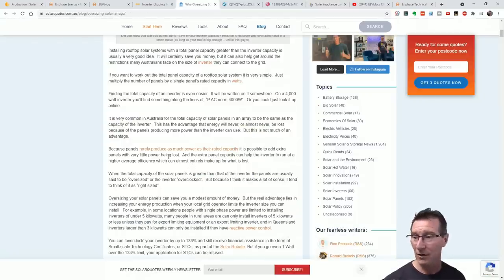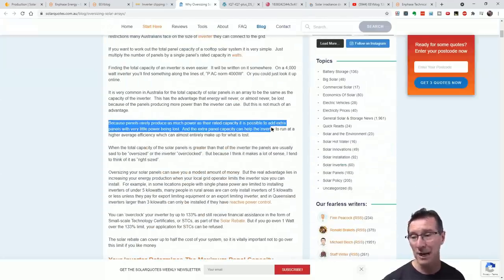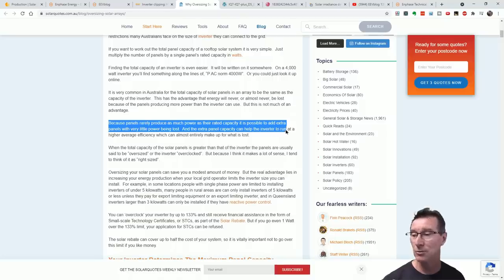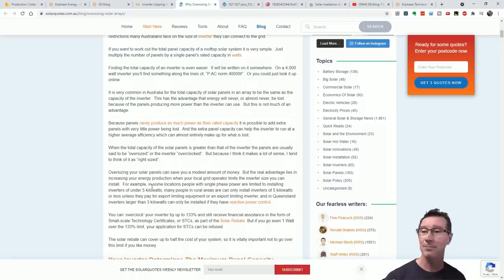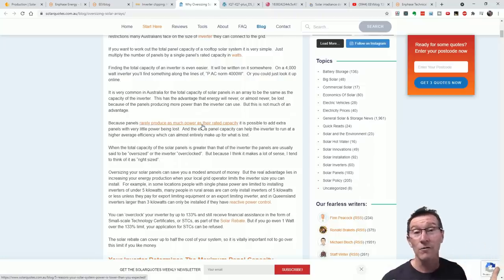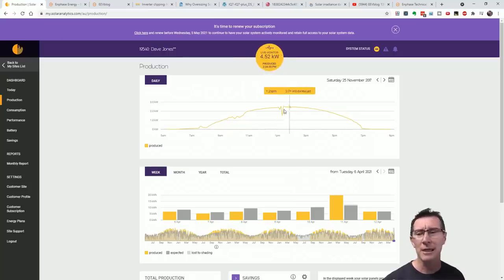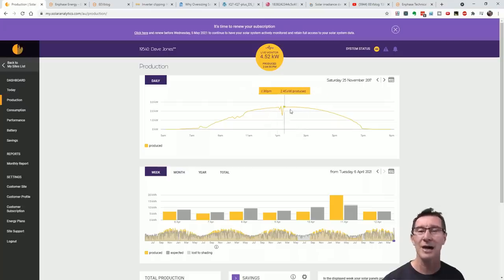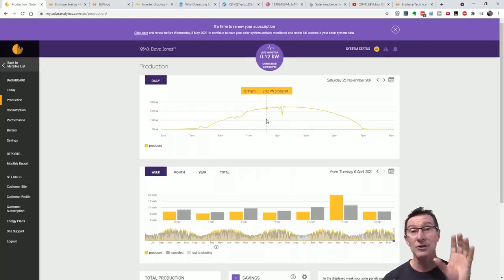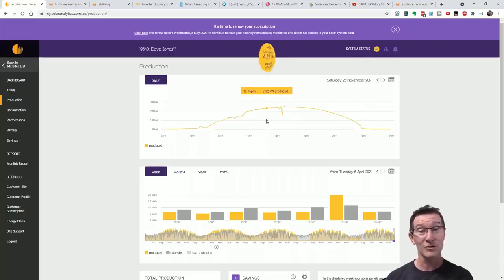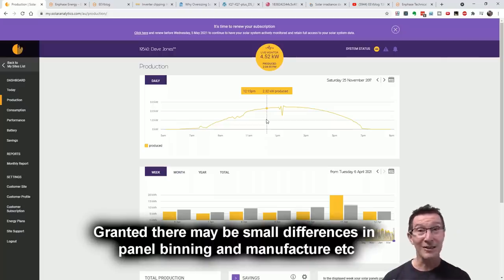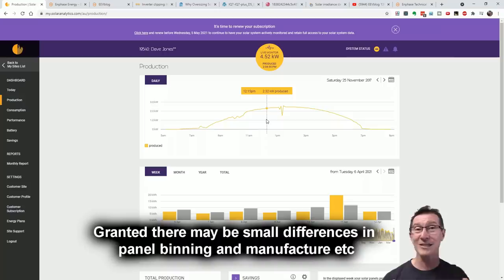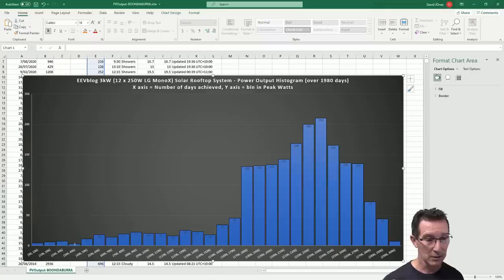Show us the data that you've analyzed. Well, if you go to this article here it says, because panels rarely produce as much power as their rated capacity, it is possible to add extra panels with very little power being lost. And somebody on Twitter brought this up and I've contacted Enphase themselves and they've said not many days per year in Sydney is going to be over that nominal 80% figure. Well I've got an existing system here which I've been measuring for the last seven and a half years with occasional data loss. I was able to take all this data and analyze it.